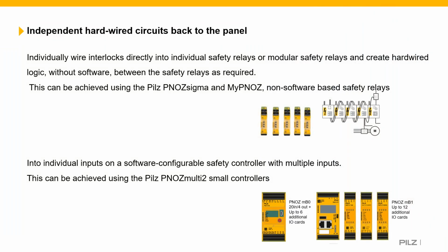We could potentially individually wire all interlocks back into their safety relays, and you can use things like the PNOZ Sigma or MyPNOZ, so typical hardwired systems that are available from Pilz, or you could go into a programmable system, a system like the PNOZmulti 2, where you can have some sort of logic control in the software that will allow you again to do different things with different guards at different times, depending on whether they're operated or not, but again can allow you to have multiple inputs onto one safety controller.